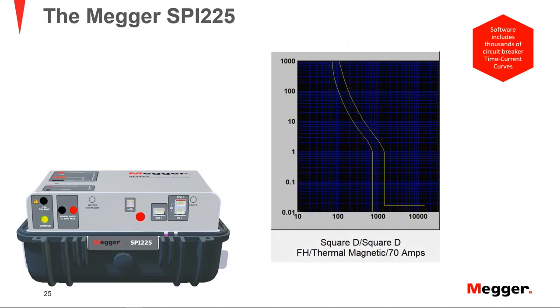Another great feature of the software is the inclusion of a very large library, right now up to close to 7,000 time current curves for the circuit breakers. I can just go into the library, select the breaker that I'm testing, and the software already has the TCC baked in, not only to display it, but also to plot the results inside the curve and immediately give you a pass or fail result. I'll show you that as well when we go over PowerDB testing. When I finish my measurements, I get my results.